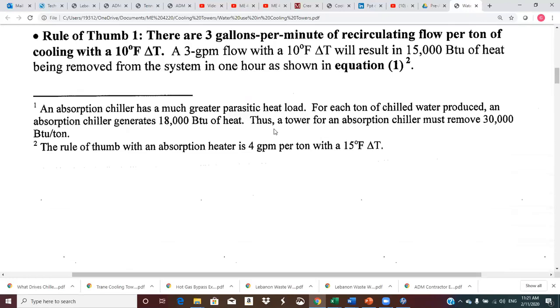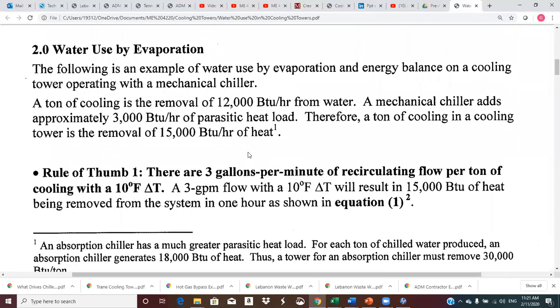We see this footnote 1. If we go down here, it says absorption chiller has a much greater parasitic heat load. For each ton of chilled water produced, absorption generates 18,000, and that 18 plus 12 is 30,000 BTUs per ton that have to be rejected. And so one rule of thumb, this is not what the Carrier program defaults to. And when you run your homework, I would go ahead and accept the Carrier program default. I think it's 3.75. But anyway, this article says that the condenser water flow on an absorption unit is 4 GPM per ton, sized at a 15-degree delta T. I think the 15-degree looks right. And this is relatively right.